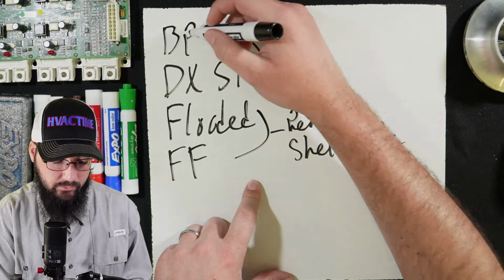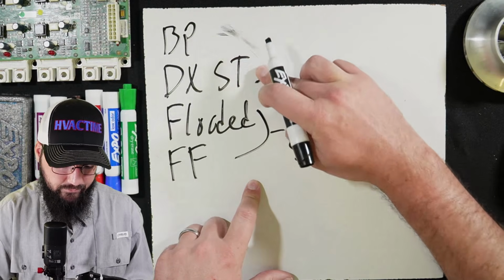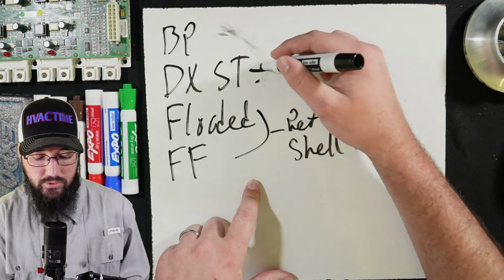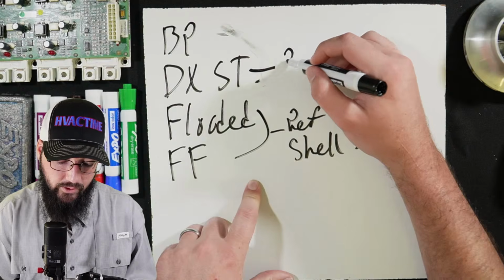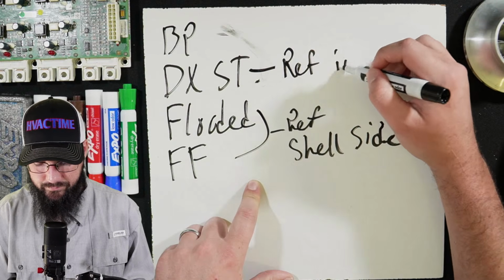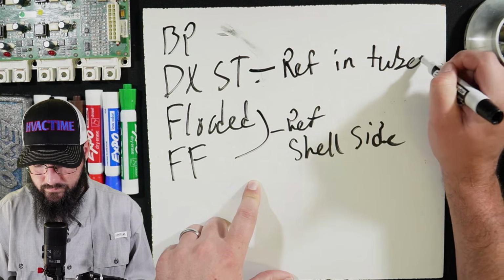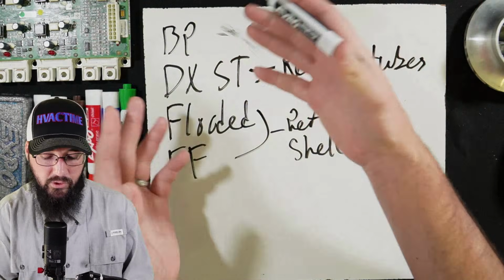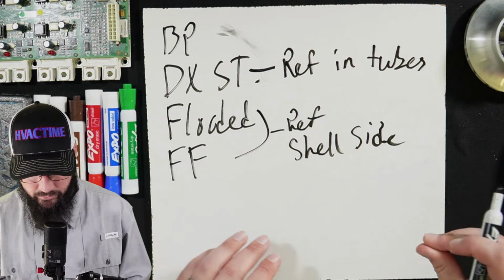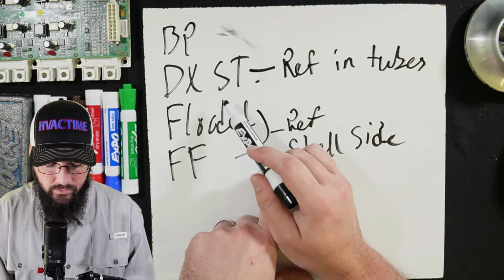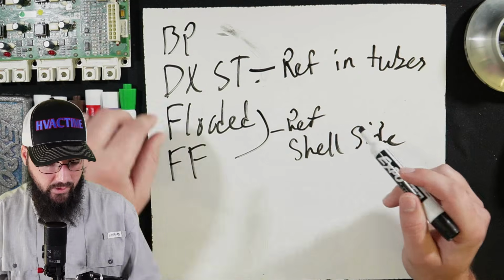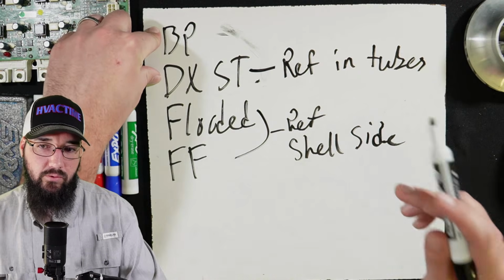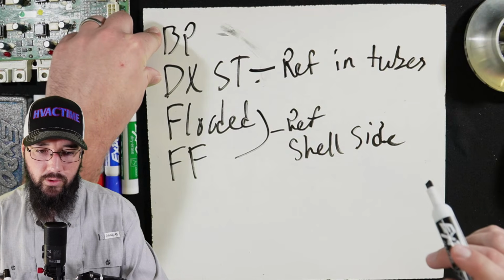Well, okay, not braze plate. For the DX shell and tube, the refrigerant is in the tubes. And then braze plate is braze plate. I don't think I need to over explain that. So that's your core difference here.